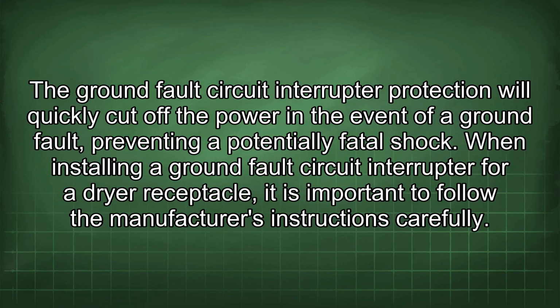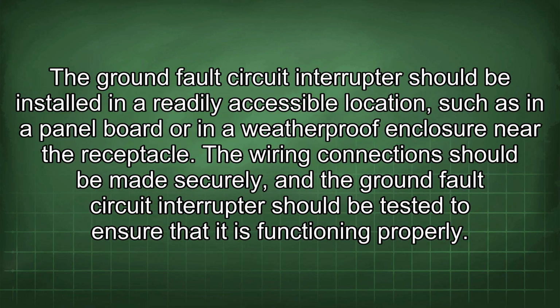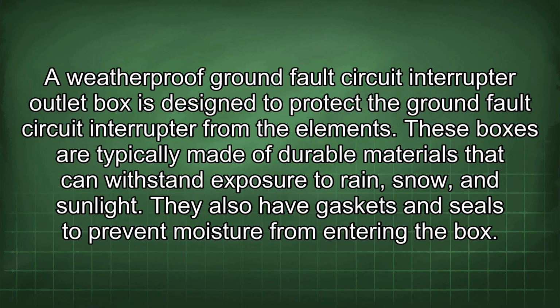the manufacturer's instructions carefully. The ground fault circuit interrupter should be installed in a readily accessible location, such as in a panelboard or in a weatherproof enclosure near the receptacle. The wiring connection should be made securely, and the ground fault circuit interrupter should be tested to ensure that it is functioning properly. A weatherproof ground fault circuit interrupter outlet box is designed to protect the ground fault circuit interrupter from the elements. These boxes are typically made of durable materials that can withstand exposure to rain, snow, and sunlight. They also have gaskets and seals to prevent moisture from entering the box.